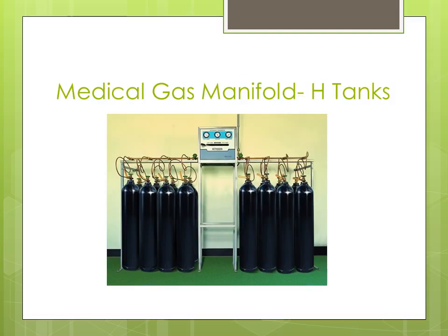Now this next one, here we go again. Again, a little concerned here. We see the manifold system. We see all these black tanks. This here could be nitrous, I suppose, and it's all tied into this bulk manifold system. But are they secure? Again, I would question whether these are secure or not. Typically, when they're secure, you're going to see a chain around them. It'll be very obvious that they're secure. So it's interesting that these are marketing images that I found, but they're not showing that they're very secure.